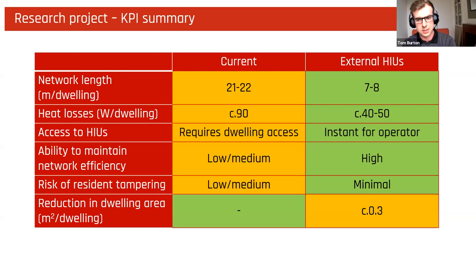Access is instant with external HIUs, which means your ability to maintain performance is high, and the risk of resident tampering, although it's not a huge impact on the conventional layout, you also completely remove that risk as well. But then at the bottom you see that it's about 0.3 meters squared per dwelling of cupboard area that you need to find space for and you need to account for in your design.